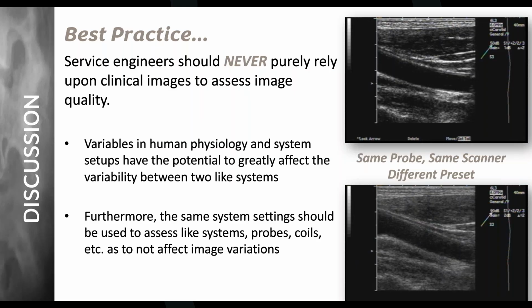It depends on the construction of a Phantom. The MRI Phantoms are solid, so with proper care, they can last indefinitely. With ultrasound Phantoms, there's 2 different kinds. There's the solid block, and did any of you watch Mythbusters? They always talk about ballistic gel. That's what the Phantom looks like, but it's not ballistic gel. It's a hard, solid material that is designed to mimic the attenuation of ultrasound in human tissue.